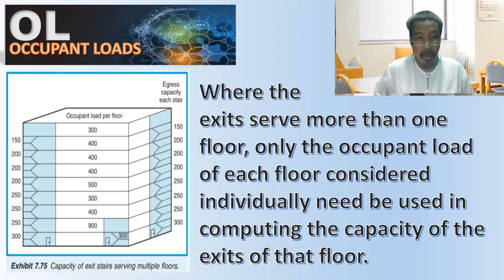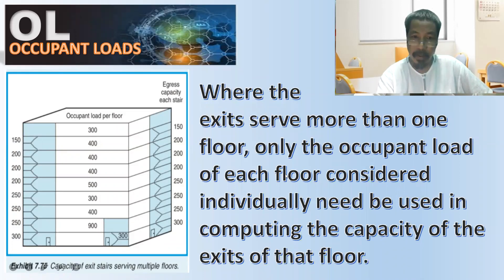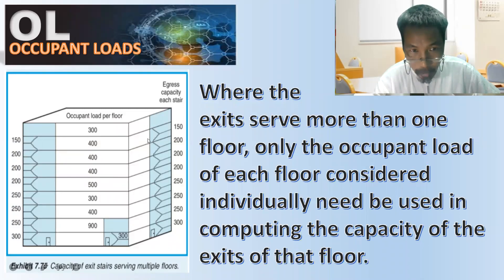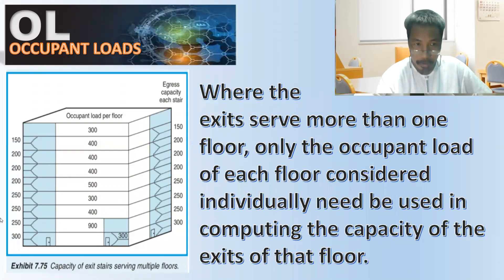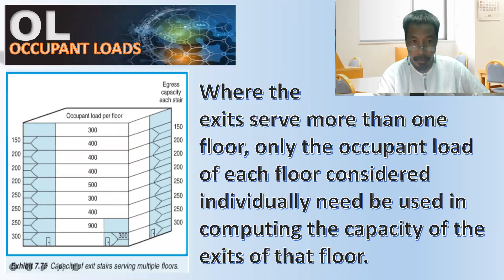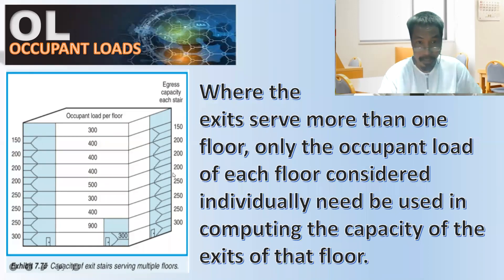The key principle is: where exits serve more than one floor, only the occupant load of each floor considered individually must be accounted for. Do not add the loads of adjacent floors together. You only consider one floor at a time and take the higher value. For example, do not add 500 and 300 to get 800 - only consider 500 because it is higher. The resulting exit capacities per floor are: 150, 200, 200, 250, 250, 250, 250, and 300.